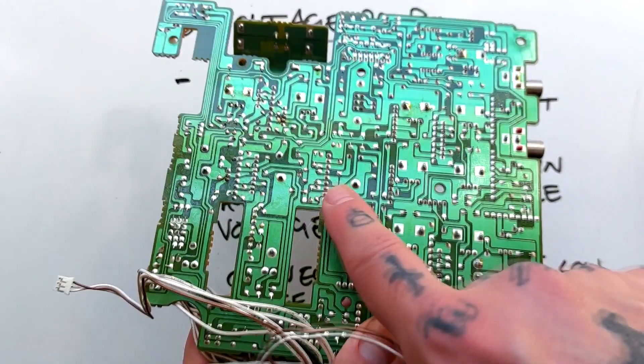Last thing: connectors should have low voltage drop. Otherwise, they steal energy from active components. Remember, we're trying to fix things that are well designed but old or neglected. One really common issue is a wire gets jostled and either breaks completely or isn't fully conductive. By not fully conductive, it's almost like there's a resistor in that wire. So if you test a wire and it has a high voltage drop, that tells you it's a bad wire that needs to be replaced.